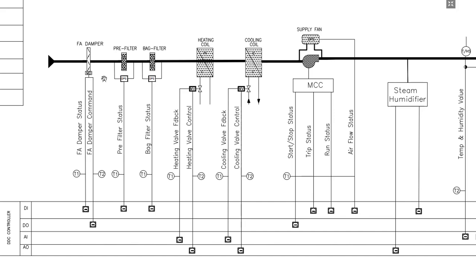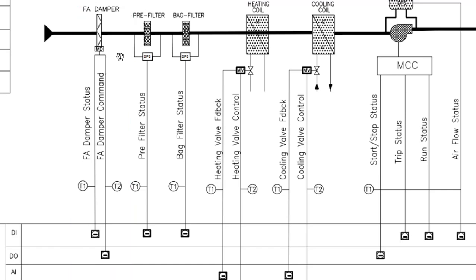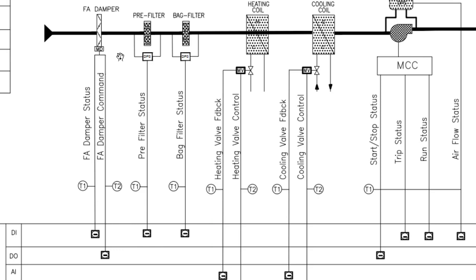Now let's talk about the components of the schematic diagram. First, the fresh air damper is shown here, which has two points — one is a command point and another is a monitoring point. Point type is also shown in the schematic diagram. The fresh air damper command uses a T2 type cable because we need power supply and command for this damper. The fresh air damper status uses T1 type, which is only a two-conductor wire. Then we have pre-filter and bag filter dirty status. We are using a differential pressure switch for monitoring the clean and dirty status of the filters. These are only DI monitoring points, and we are using T1 cable because we need only a two-conductor cable here.